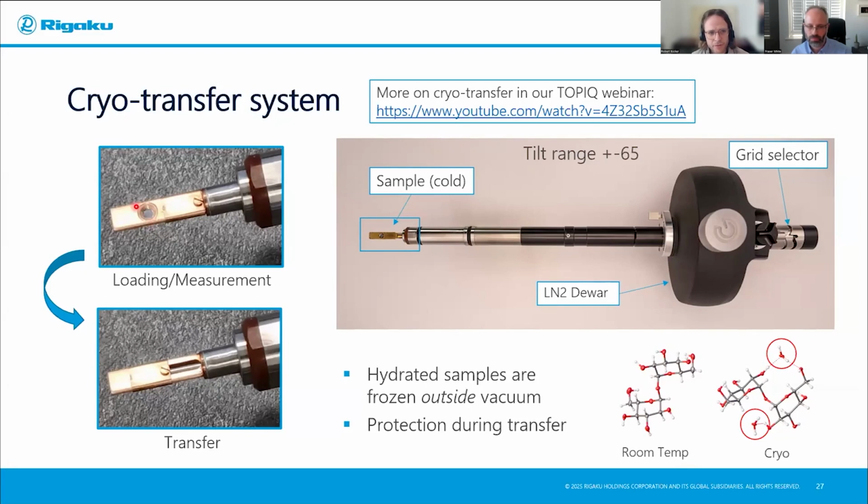So you have an O-ring seal at the tip, and then you can retract your grid into the holder where it's perfectly sealed inside an inert atmosphere and get it then into the diffractometer. So for optimal air-free transfer performance, you can have even different holders, but even with a cryotransfer holder, you can be a bit creative and handle air-free transfer and air-sensitive samples very nicely.